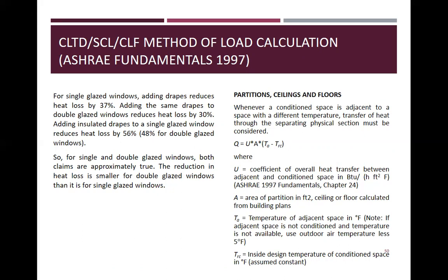Now next is the partitions, ceilings, and floors. Whenever a conditioned space is adjacent to a space with a different temperature, transfer of heat through the separating physical section must be considered. So Q is equal to U A times (T sub O minus T sub RC), where U is the coefficient of overall heat transfer between adjacent and conditioned space in BTU per hour square foot Fahrenheit as stated in 1997 Fundamentals, chapter 24. A is the area of partition in square feet, ceiling, or floor calculated from building plans.